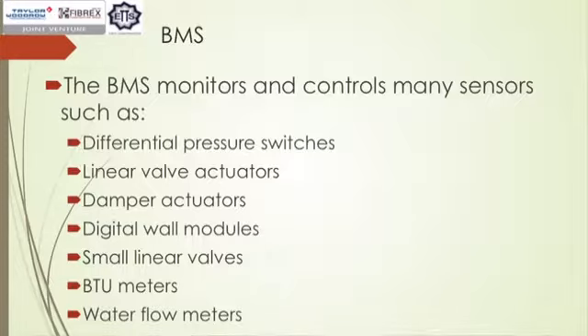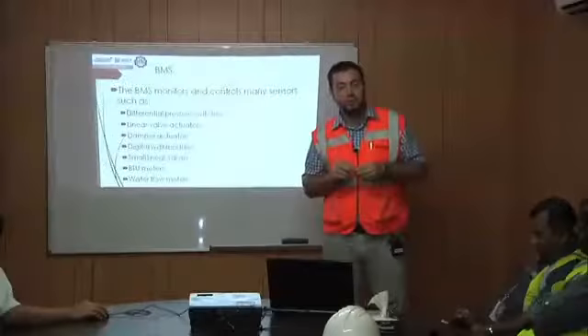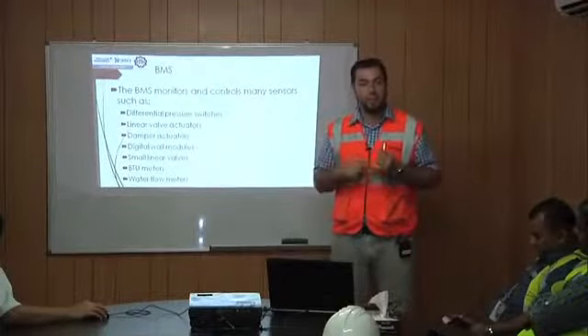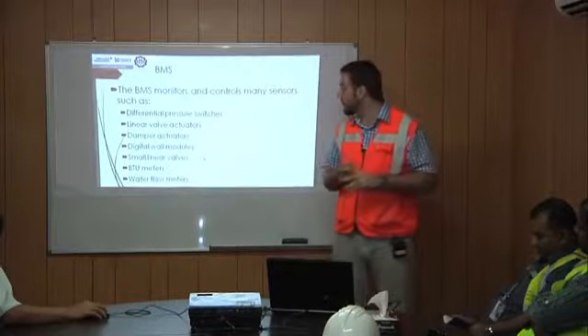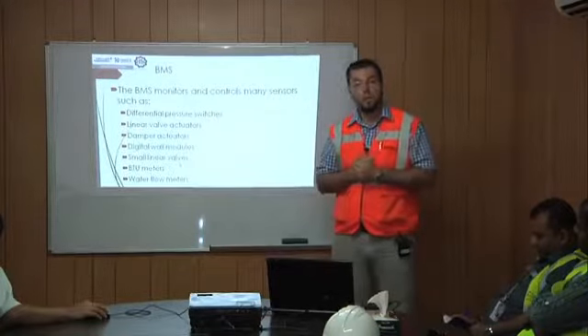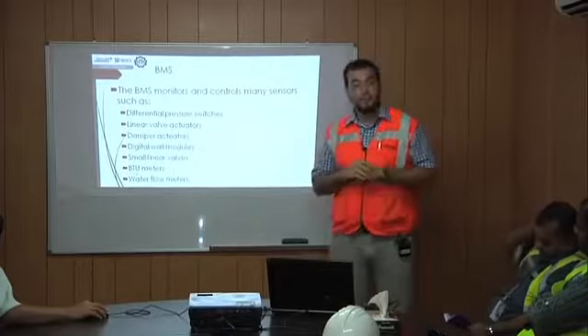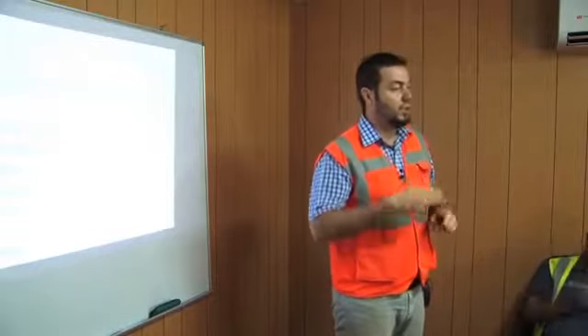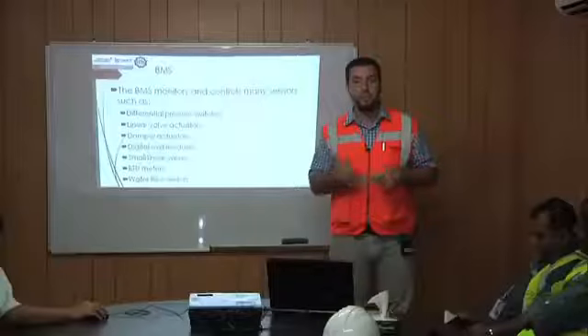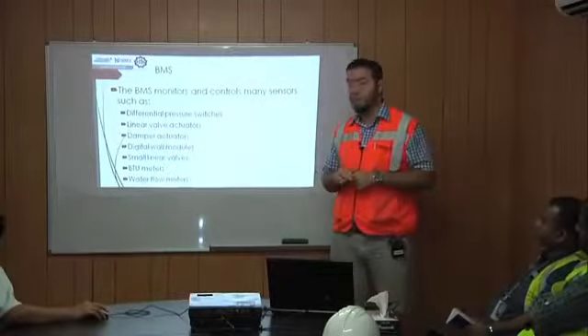We've got small linear valves. These are installed on the fan coil units. In the bridge area, we have 3, and we have in the trash room, and we have in the UPS room. We've got BTU meters. We have 6 BTU meters in total. Each BTU meter has 2 temperature sensors on the supply, on the return, and we've got 1 flow meter. All of these are integrated with the BTU.